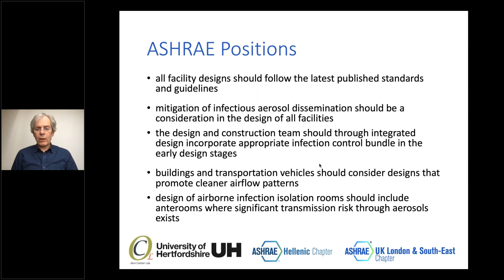Design of airborne infection isolation rooms should include anti-rooms, surrounding rooms where significant transmission risk through aerosols exists. The following should be included based on risk assessment: enhanced filtration with higher minimum efficiency reporting value filters over code minimum, upper room UVGI irradiation with possible in-room fans as a supplement to supply airflow, local exhaust ventilation for source control, personalized ventilation systems for certain high-risk tasks, portable freestanding high-efficiency particulate air HEPA filters, and temperature and humidity control.